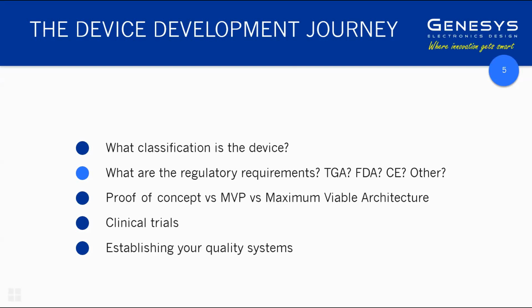Ironically, although the FDA had been considered the higher bar to jump, it is now probably the most accessible regulatory pathway because of the difficulties in Europe caused by the medical device regulation.